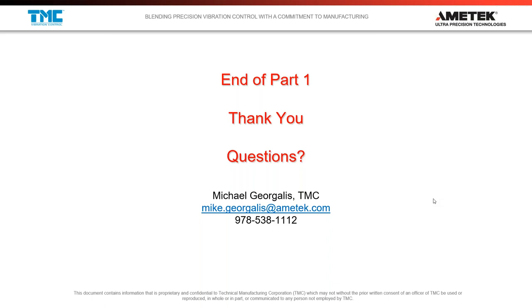Yeah, that's a great question. If it's a simple optical table, then house air is all that's needed at 80 psi. That's at the very simple level. If you start thinking about active vibration cancellation systems, and you have a known vibration problem, or you've had a vibration survey done and you've noticed that there could be resonant frequencies that might be a problem for you, I really think you should join next week's session to talk a little bit more about vibration cancellation, just to make sure that you're putting in the right type of table.